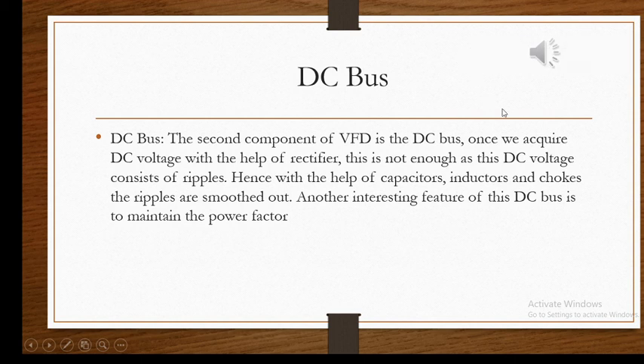The second component of a VFD is the DC bus. Once we acquire DC voltage with the help of a rectifier, this is not enough because this DC voltage consists of ripples. Hence, with the combination of capacitors, inductors, and chokes, these ripples are smoothed out in the DC bus. Another interesting feature that the DC bus performs is to maintain the power factor of the motor.